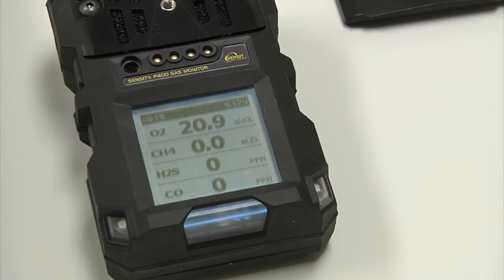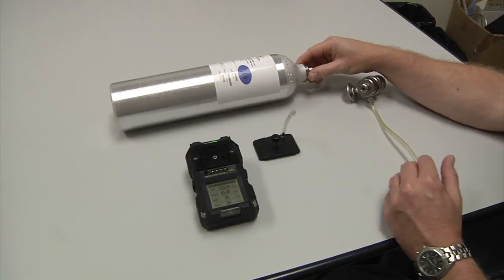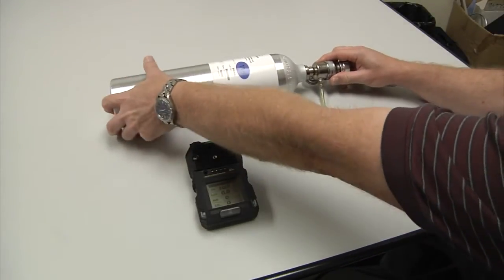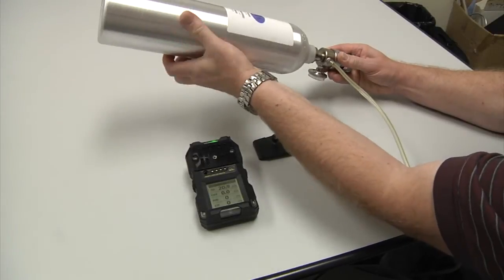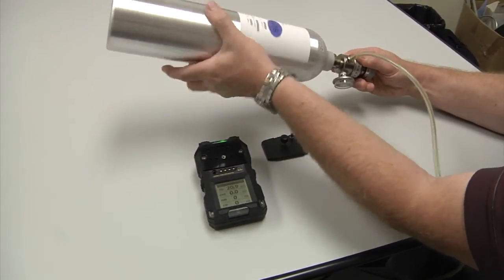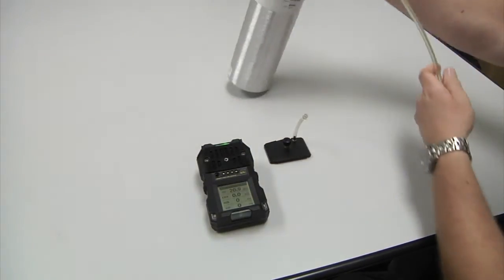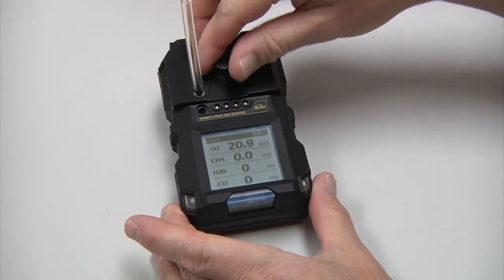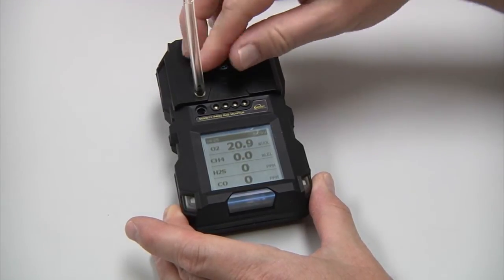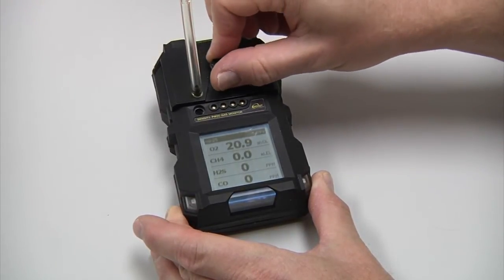Once the instrument is fully powered up, we want to wait an additional five minutes before we start the calibration process. First, attach the regulator to the gas cylinder, and attach the calibration cup to the instrument with the thumb screw. This just has to be snug, not tight.